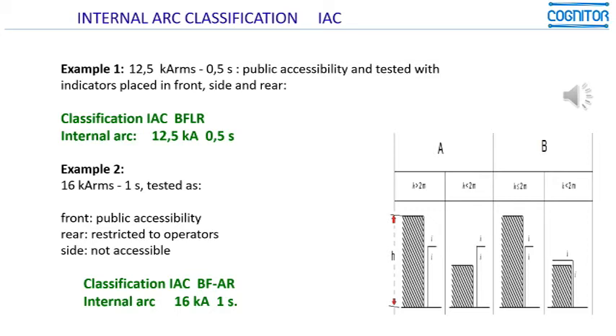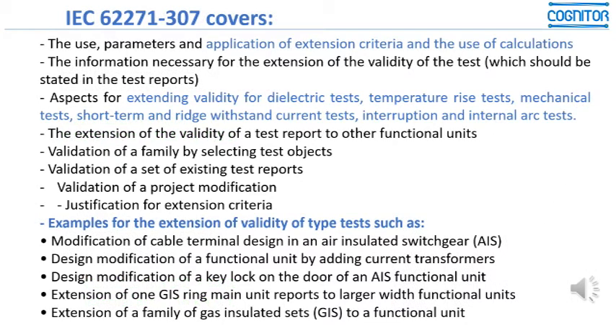If it was tested this way under the rules of IEC 62271-200, it would remain valid even after a modification — such as a cable terminal design change in one AIS. This is a simple modification, but under today's view, if something is modified, many times the user considers it a new equipment and wants to retest. This can be avoided by this new IEC document.